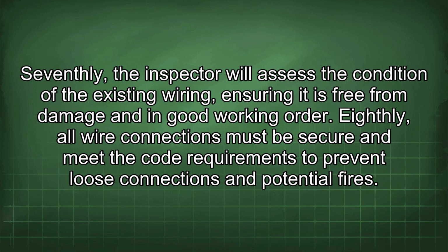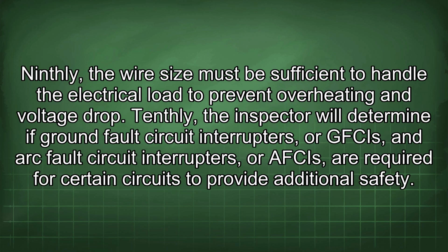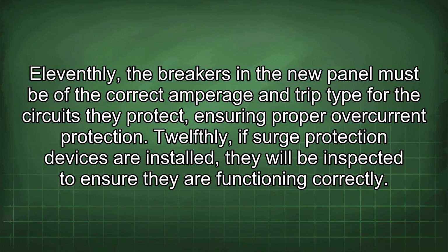Seventhly, the inspector will assess the condition of the existing wiring, ensuring it is free from damage and in good working order. Eighthly, all wire connections must be secure and meet the code requirements to prevent loose connections and potential fires. Ninthly, the wire size must be sufficient to handle the electrical load to prevent overheating and voltage drop. Tenthly, the inspector will determine if ground fault circuit interrupters, or GFCIs, and arc fault circuit interrupters, or AFCIs, are required for certain circuits to provide additional safety. Eleventhly, the breakers in the new panel must be of the correct amperage and trip type for the circuits they protect, ensuring proper overcurrent protection.